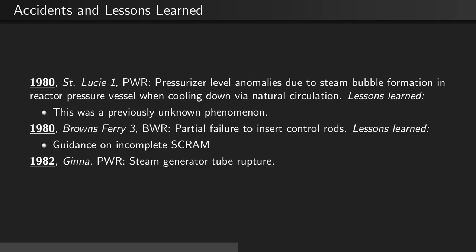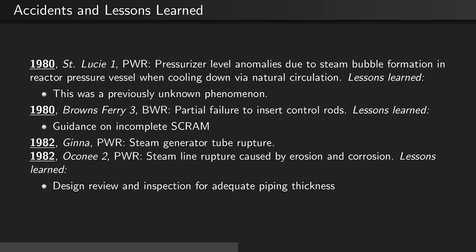In 1982, at the Ginna, PWR, a steam generator tube ruptured. Also in 1982, at Oconee 2, a PWR, there was a steam line rupture caused by erosion and corrosion. This led to design review and inspection for adequate piping thickness.